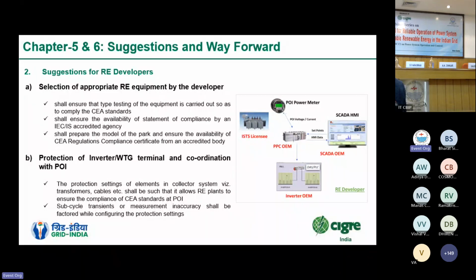So the next point is protection of the inverter terminal and coordination with the POI. This has been explained. One point remains the same: during the voltage measurements at the point of interconnection, any protection-based tripping which requires immediate tripping of the equipment, say for high voltage ride-through, for voltages above 1.3, there is a provision for immediate tripping. That should not be dependent on sub-cycle measurements. At least a 1-2 cycle delay should be there so that some RMS value or other appropriate values are available, so that in transients the equipment does not get tripped.